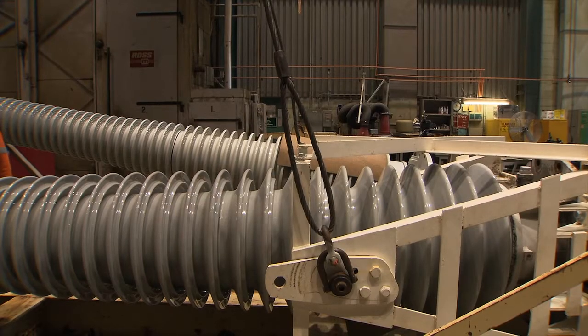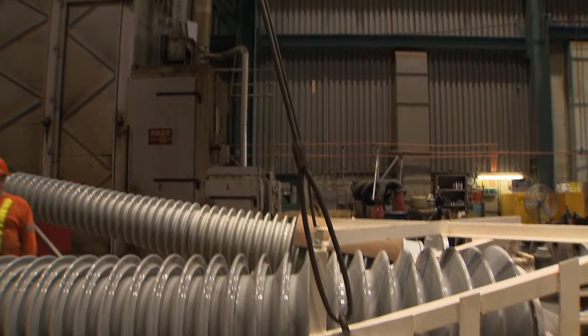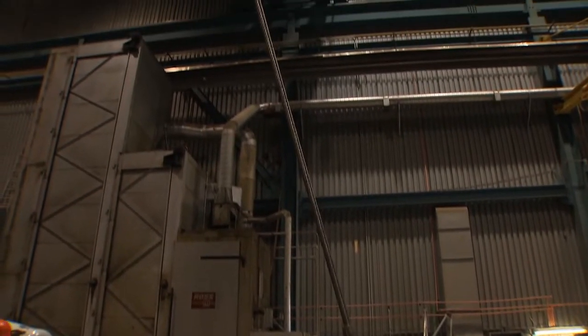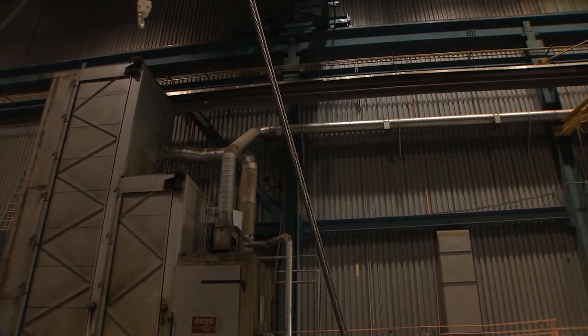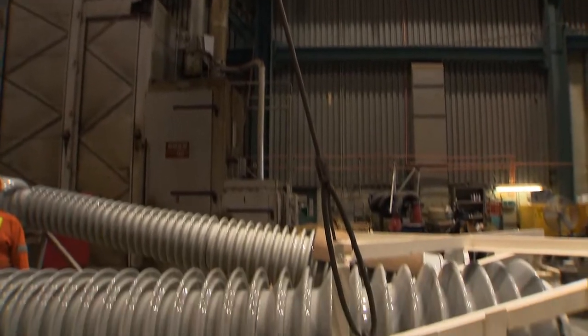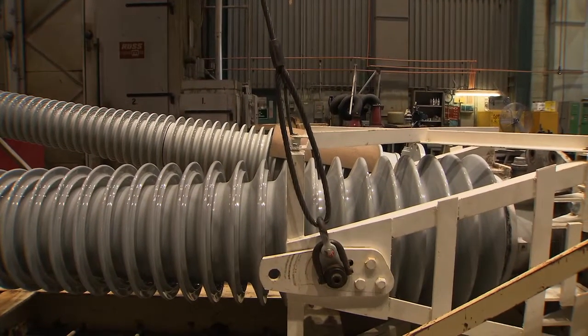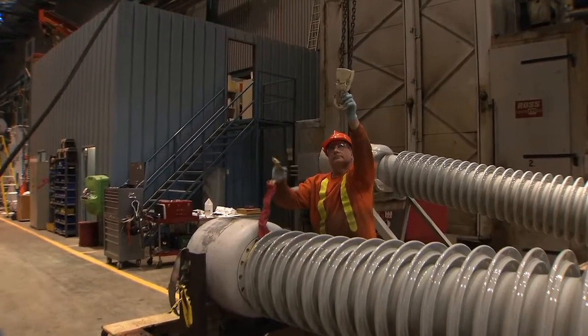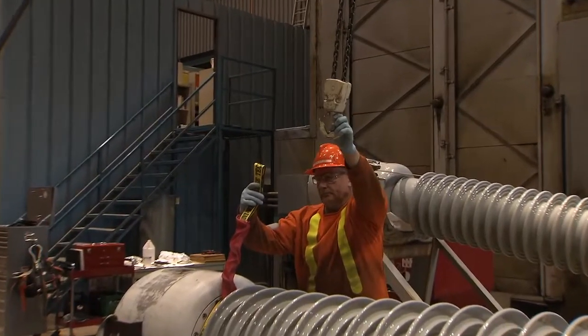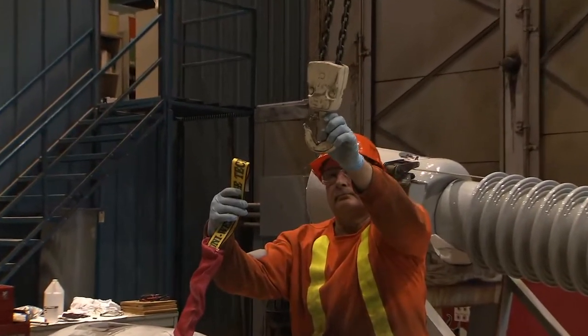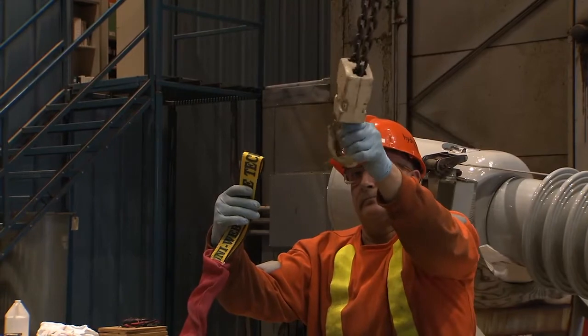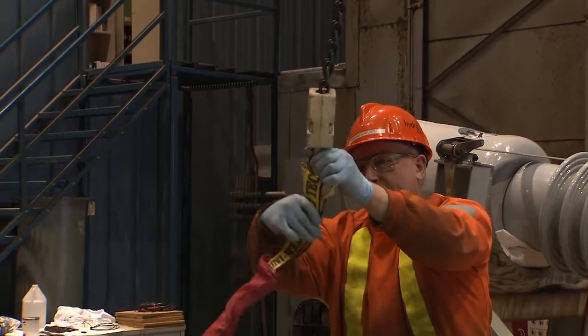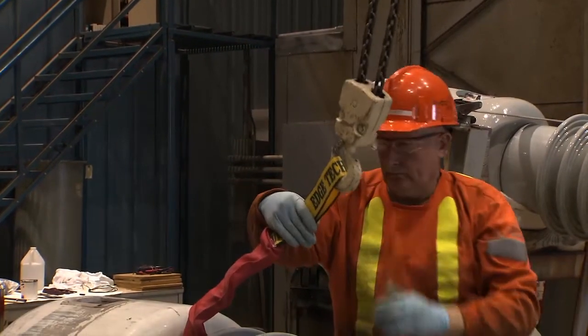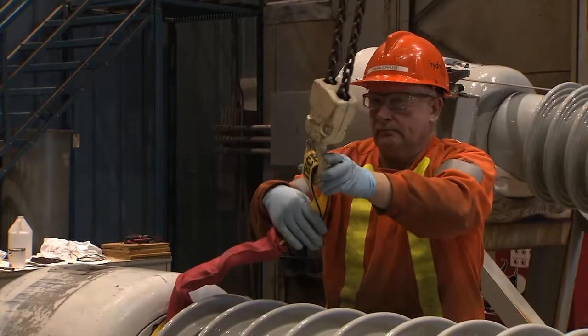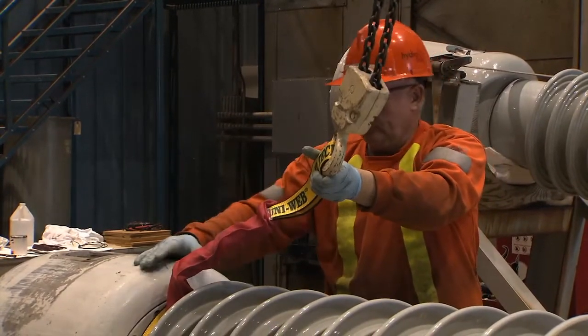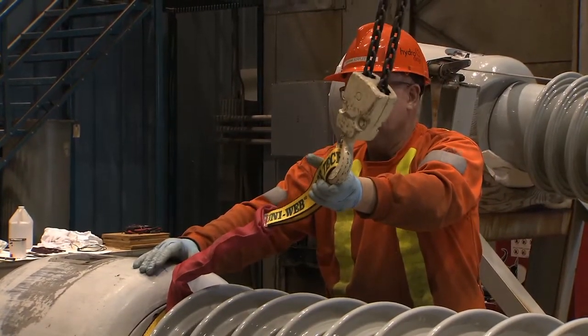The metal crane cables are attached to the sides of the lifting jig and extend to each side of the multi-point lifting beam suspended above the bushing. Lower the hoist hook of the electric portable hoist that's suspended in the center of the lifting beam, and attach the end of the sling choked around the top of the bushing to the hook. Okay. So now I'm just going to do a little centering of this device.